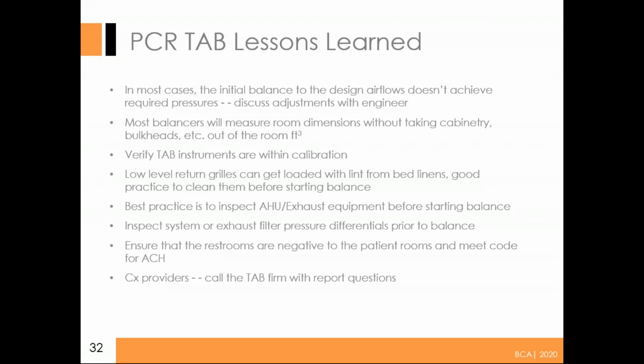The other thing about exhaust with turn vanes and elbows, something you can't see, but we find that through the years, these things will load up and they will start really cutting your exhaust down into the space. So that's something to be aware of if you're going back to these rooms multiple times through the years. You know what to start looking for, and you know what your exhaust has been doing all these years, and all of a sudden it just slowly starts tapering off. It's something else to start looking at, doing static pressure of the profile of your ductwork or whatever to find those obstacles.